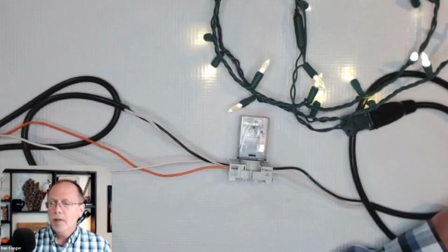Now, I think another question for y'all is, can I do that with conventional wire? Absolutely, that's really easy. For that, on your conventional wire board, I need to have a connection to the common and a connection to one zone wire, one terminal wire. So I need to have one dedicated zone on here that I can use, and I need to run those directly to the relay. Honestly, the relay might reside in a cabinet or a pedestal or something like that. We can turn that off, then we do that - these leads would then run to the relay, and we would just skip that bicoder component, and that'll allow it to run.